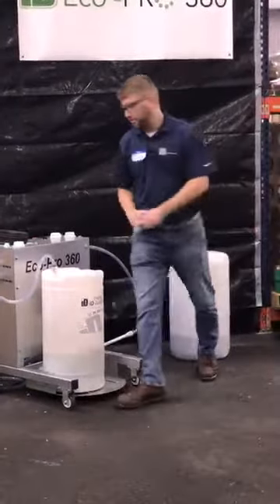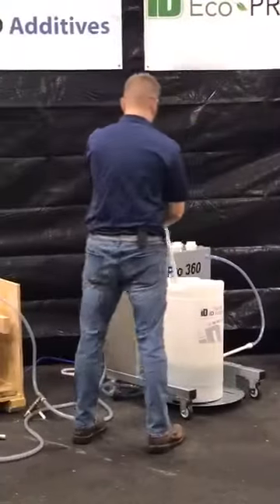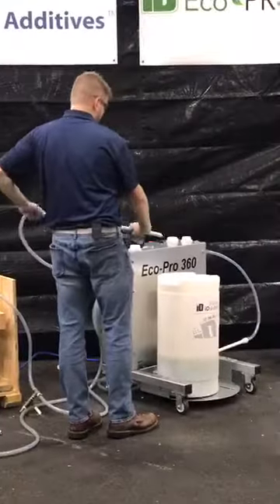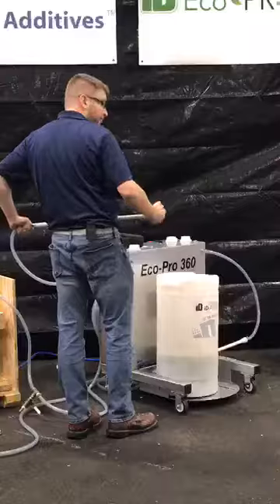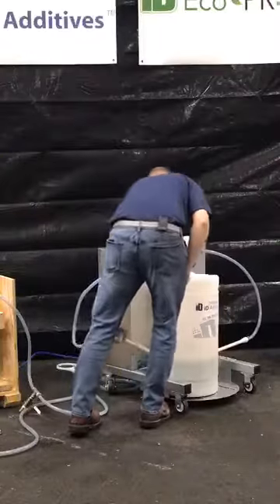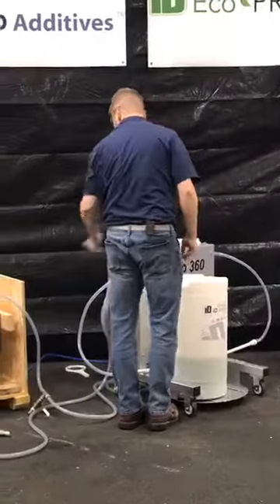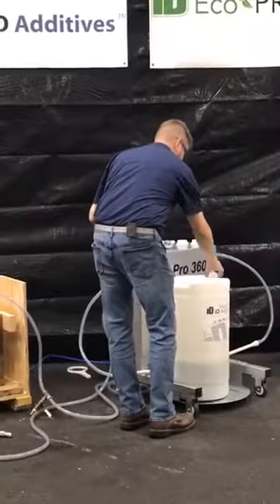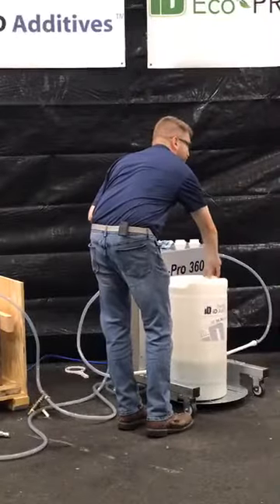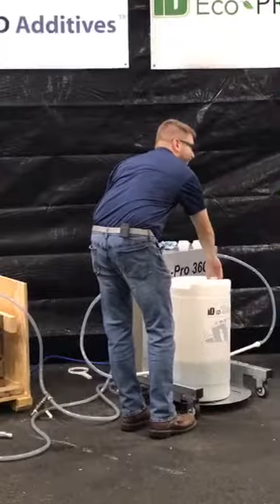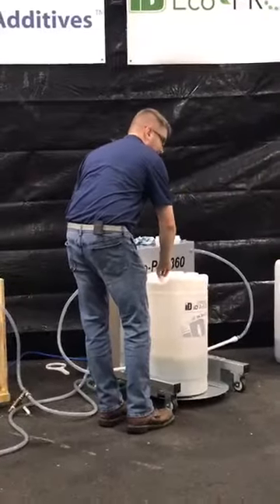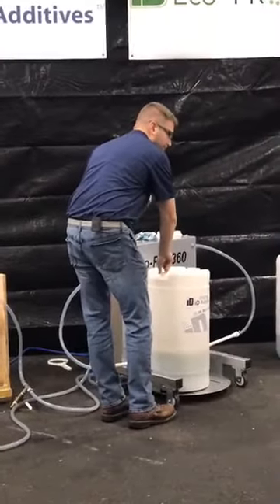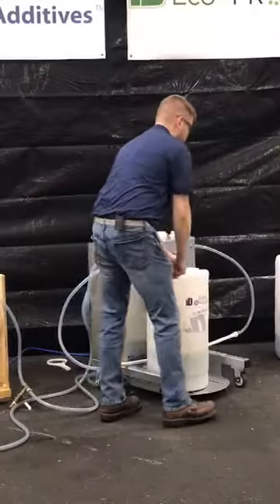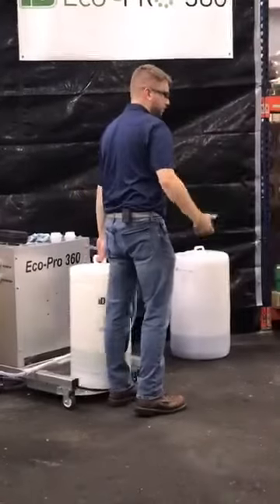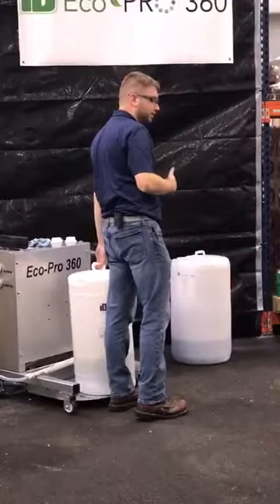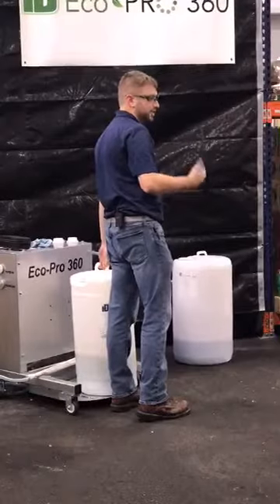I'm going to flush these. Based on the pictures that I saw, I'm going to flush it for 1.5 hours. That gives us a little bit over the standard hour, but the cooling passages, I mean, I've seen some that have a 32nd to a 64th. This is kind of in between there. So just experience tells me I could flush for 1 hour, but I'm not going to get everything off of those lines, and I obviously want you guys to be able to see that.